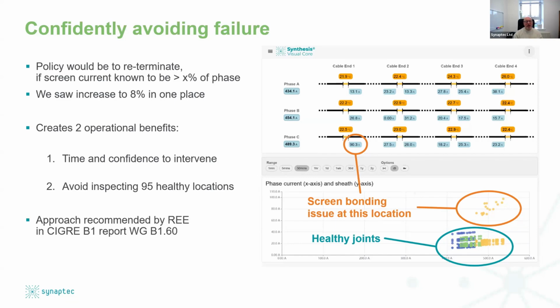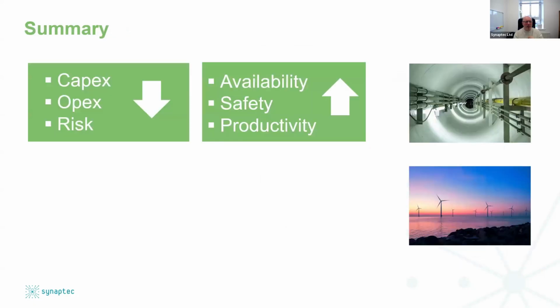Now, this approach is actually quite well documented, and those of you with access to the CIGRE papers, or the B1 group reports that I've put on the screen, it's actually recommended by Red Eléctrica de España. So that's the transmission operator of Spain, that says, if I can see these screen currents, I can see the cable failures I'm really worried about that otherwise I can't see conventionally. And all we're doing is making that possible and giving you that real-time visibility and control and the ability to know exactly where to go and when to intervene.